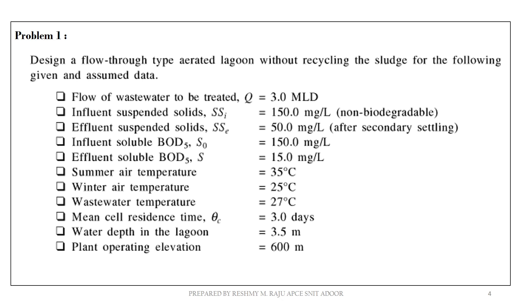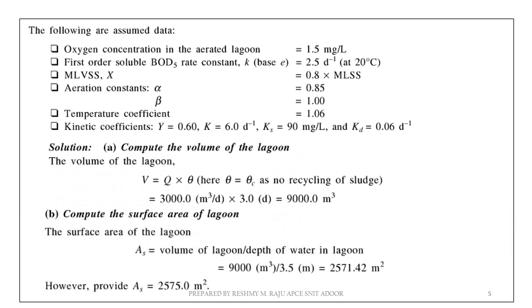We are going to study a problem: Design a flow-through type aerated lagoon without recycling the sludge. Given data — flow of wastewater: 3 MLD; influent suspended solids: 150 mg/L; effluent suspended solids: 50 mg/L; influent soluble BOD: 150 mg/L; effluent BOD: 15 mg/L; summer air temperature: 35°C; winter air temperature: 25°C; wastewater temperature: 27°C; mean cell residence time (θc): 3 days; water depth of lagoon: 3.5 m; plant operating elevation: 600 m.